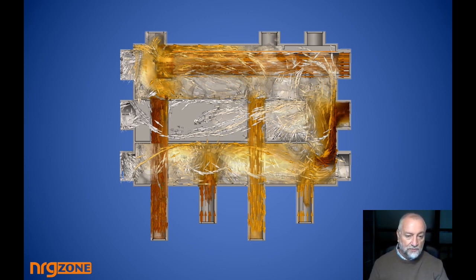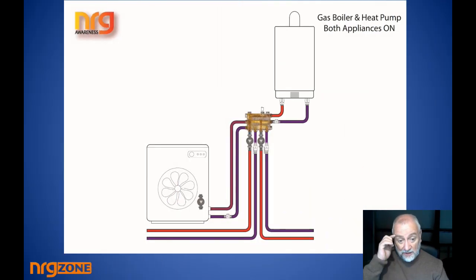So if we move on and look at the scenario where both appliances are working. Now the coldest water is coming back in the dark purple color here on A2 and B2 into the bottom chamber, and then down into the heat pump, around the heat pump, across the middle chamber, immediately before it gets to the zones, picked up by the gas boiler, raised to a higher temperature and delivered in through the internal pipe to the top left hand corner under T1, and then it feeds across and supplies the zones. And so the heat pump is now being used to preheat the gas boiler.